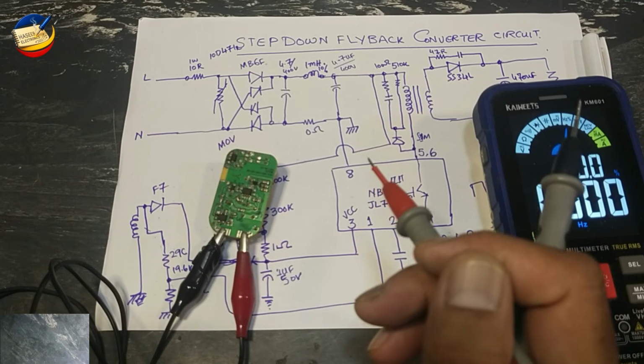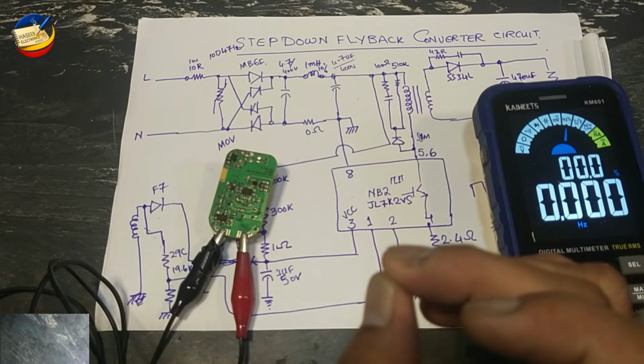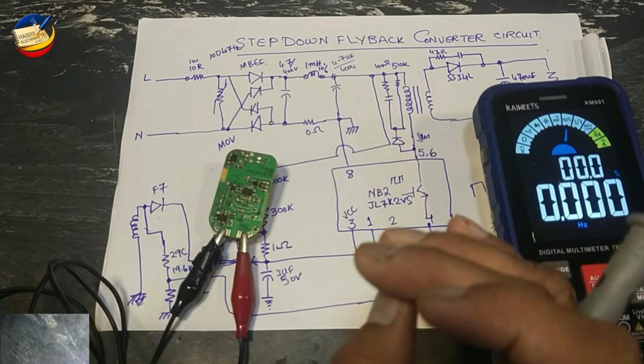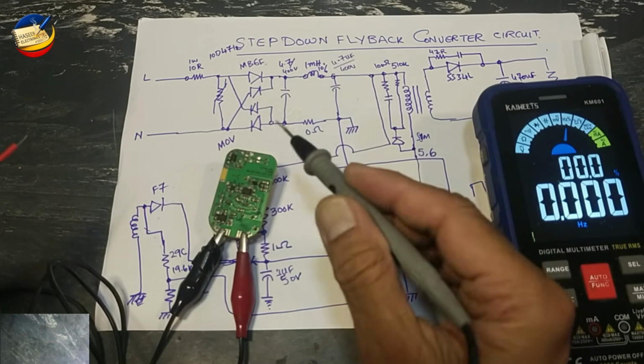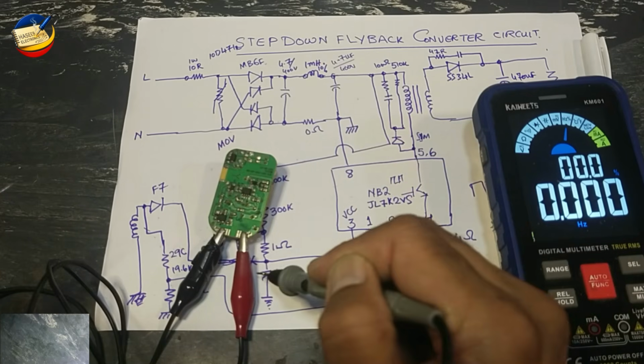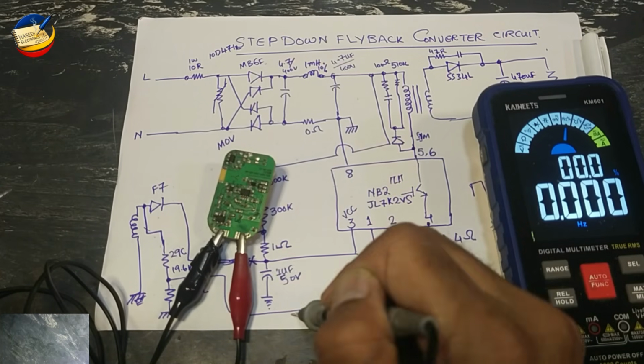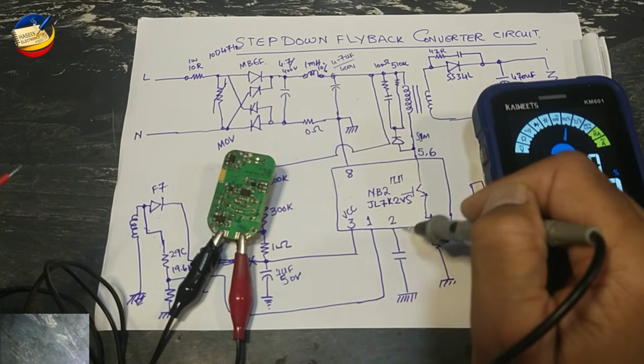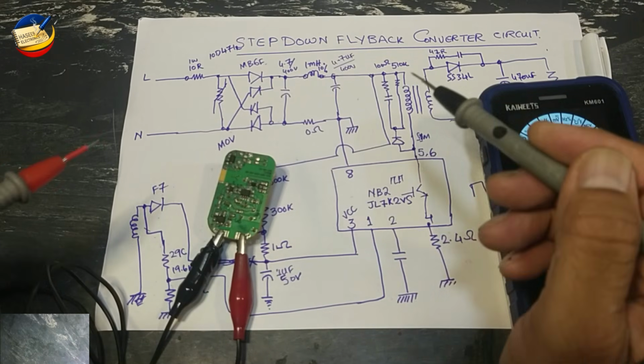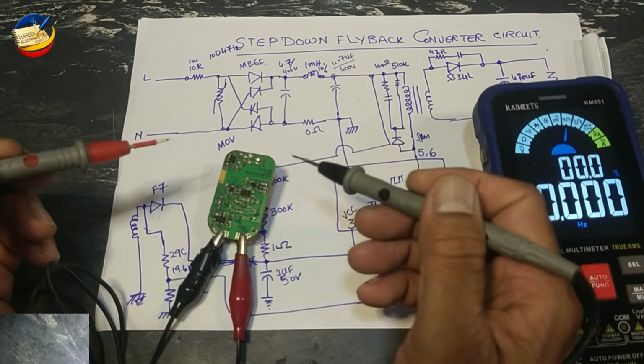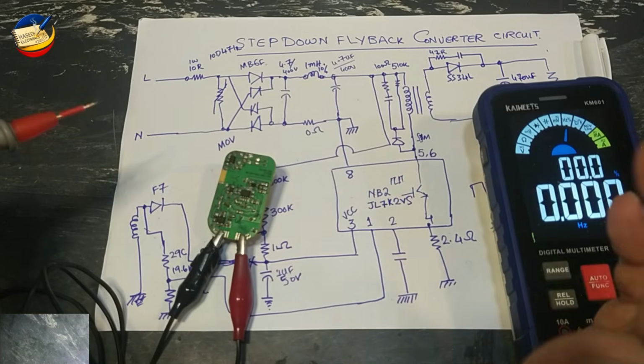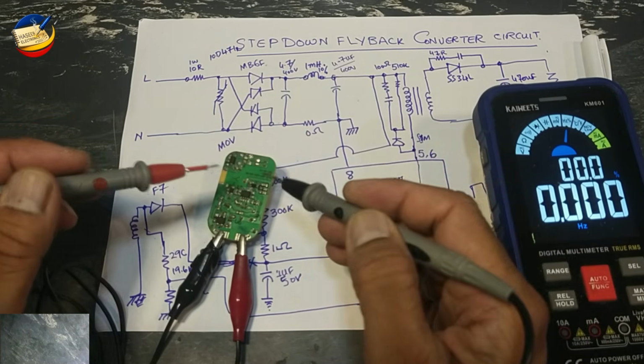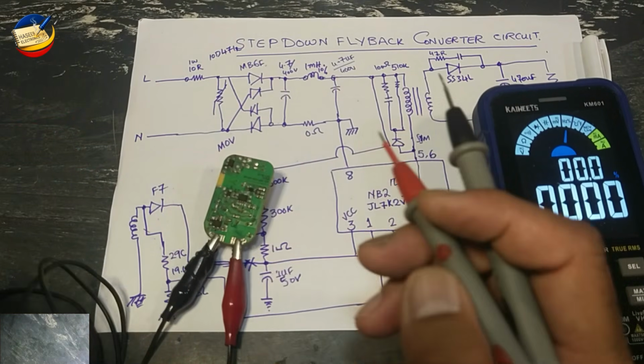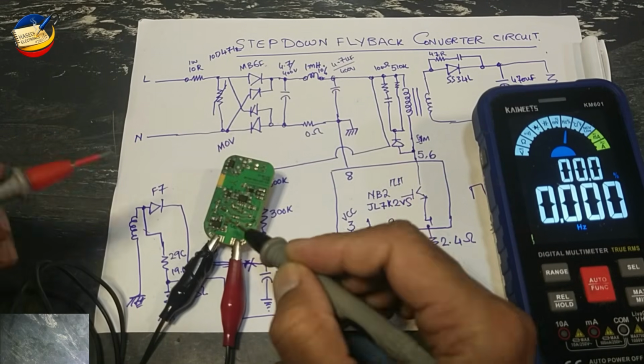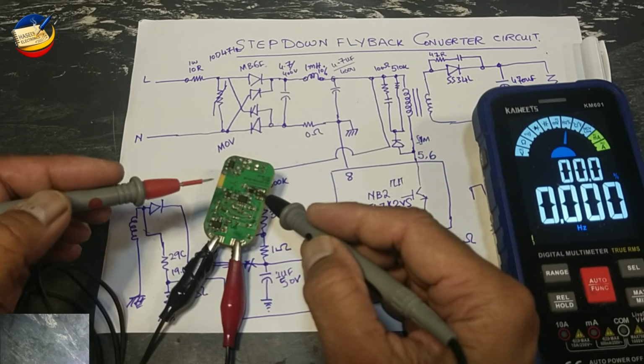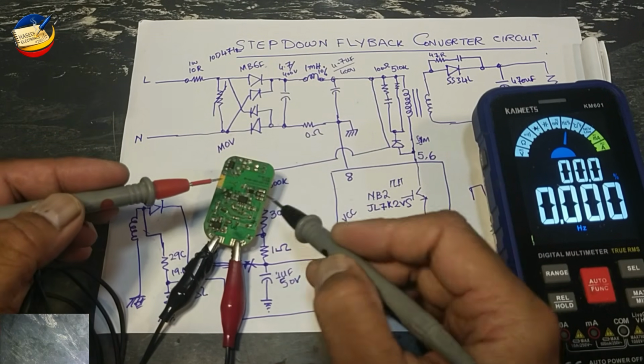When we connect a load, the zero crossing detector and feedback network provide information to the IC that there is a load. If we cannot find output, the IC might be damaged, or sometimes the transformer winding is open circuit. In that situation, we remove power, discharge the capacitors, and check continuity or resistance of the primary winding.